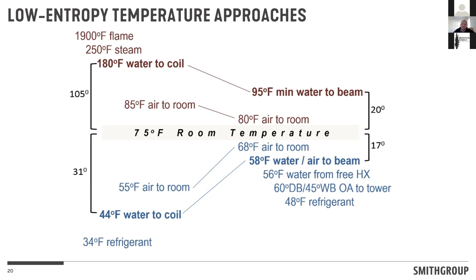And so one of the biggest things that we do on the design side is reimagine the regime for temperature distribution. When we go to hydronic distributions, like with chilled beams, chilled boxes, we can go to 95 degree delivered water, with a 20 degree delta T between the space temperature that we're trying to get to and the temperature of the water that we're delivering. This gets even more beneficial when you look at expanded thermal comfort, mixed mode components with natural ventilation. We have way more flexibility with these temperatures, but making stuff really hot just to get back to neutral is insane. And heat pumps aren't going to do it. But we can certainly make very efficient heat pump systems that are delivering 95 degree water. I can give you a COP of 4 if I'm making 95 degree water.